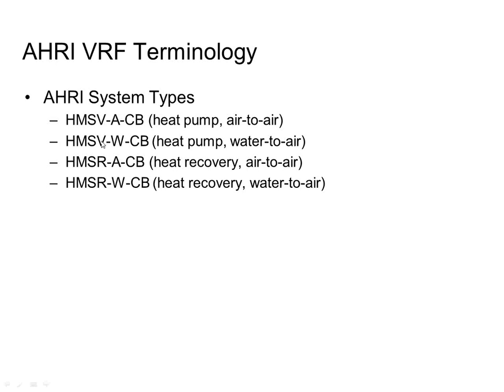So the fourth digit, if it's a V, it means it's a heat pump. And in the case of VRF, that means that it can be either in the cooling mode or in the heating mode, but it cannot do both simultaneously. If that fourth digit is an R, that means it's a heat recovery VRF system. That means it can do heating and cooling simultaneously. So some zones get heat, while other zones get cooling at the exact same time. So those two systems are rated a little bit differently from each other.